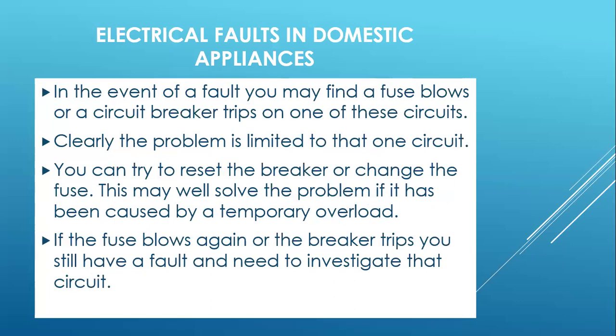In the event of a fault, you may find a fuse blows or a circuit breaker trips on one of these circuits, meaning the problem is limited to that circuit. You can try resetting the breaker or changing the fuse, which may solve the problem if it was caused by a temporary overload. But if the fuse blows again or the breaker trips again, you still have a fault and need to investigate that circuit further to identify the cause.